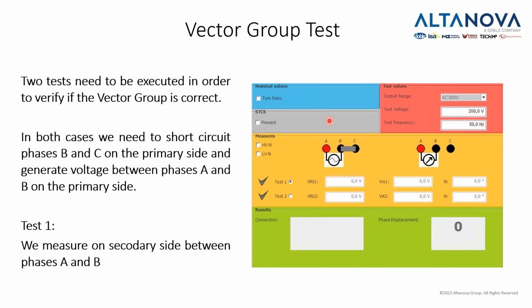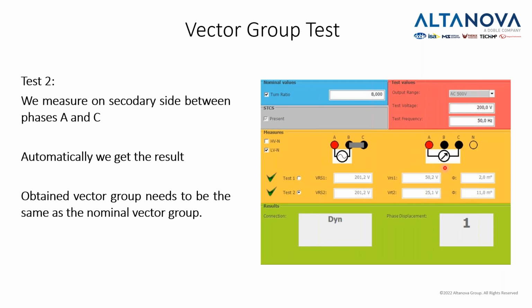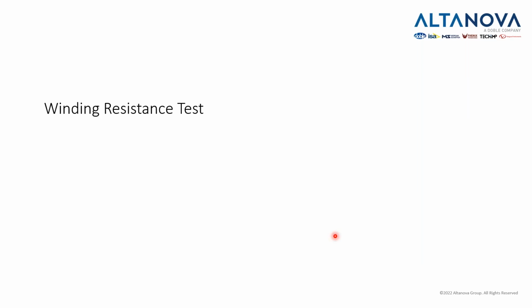With our devices, you can do two tests to identify the vector group. In both cases, we are generating on the primary side between phases A and B with B and C short-circuited, and we are measuring in our first test between phases A and B, and in the second test between phases A and C, and we obtain the vector group of our transformer, which needs to be exactly like the one which is written on the nameplate of the transformer.